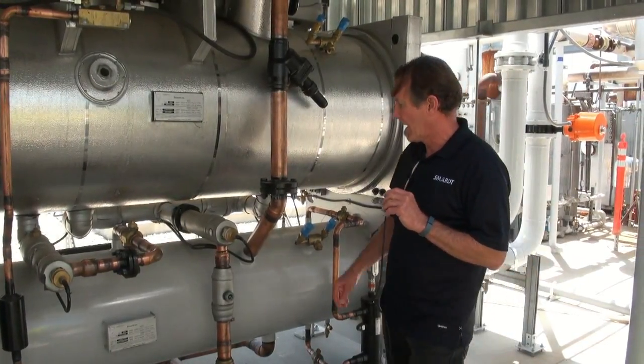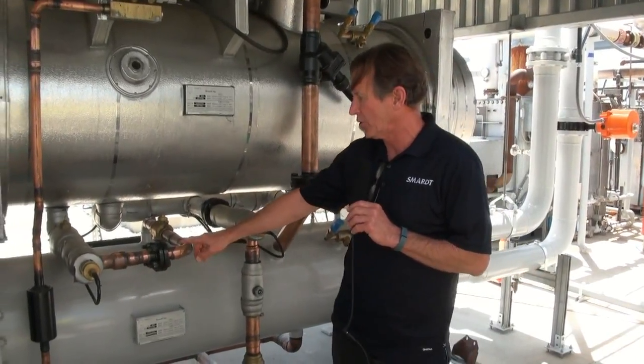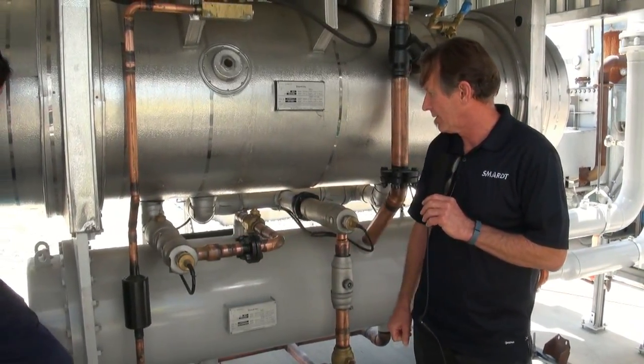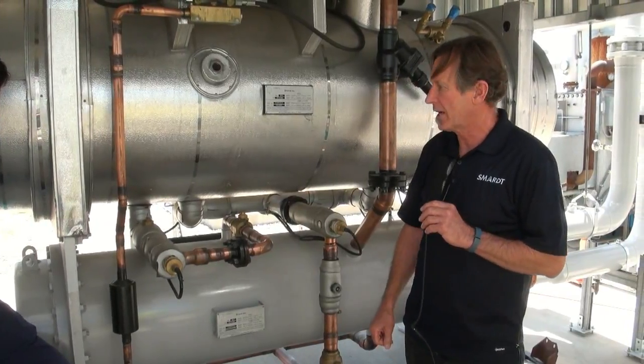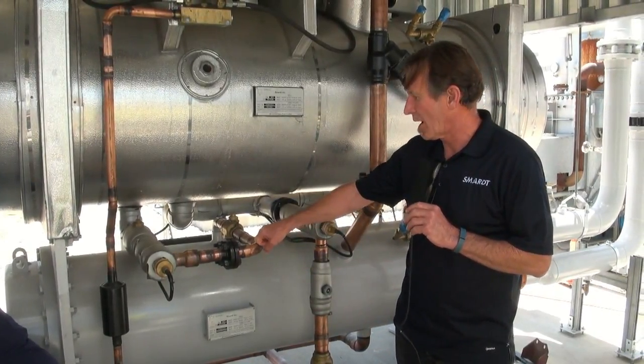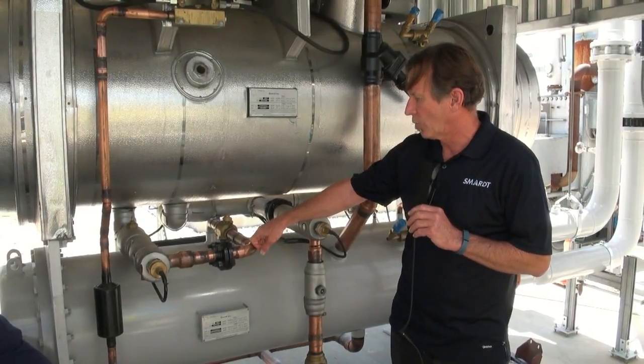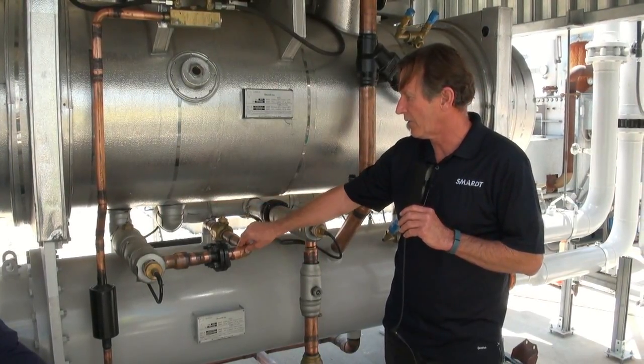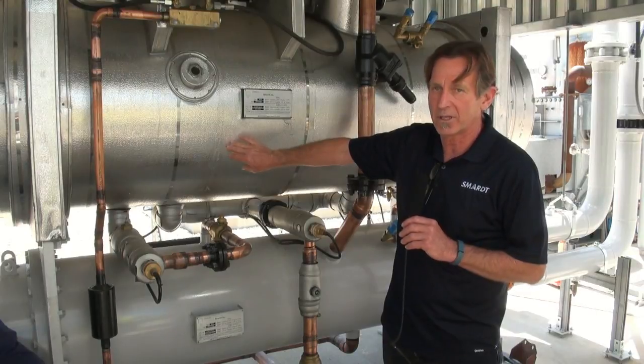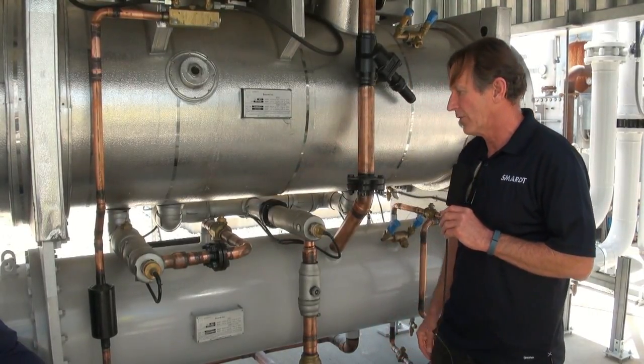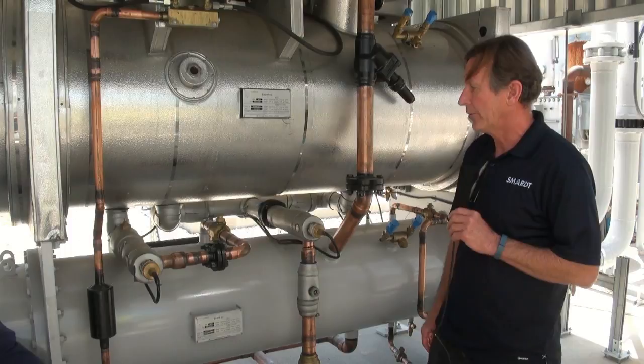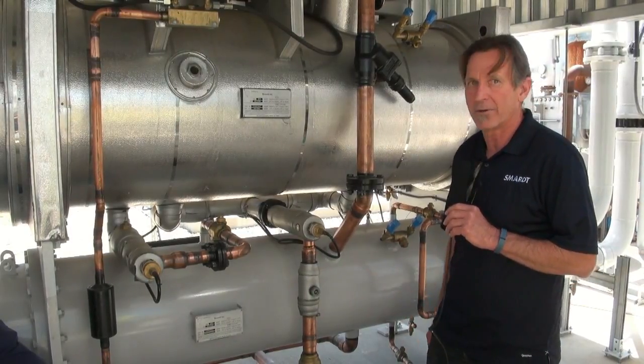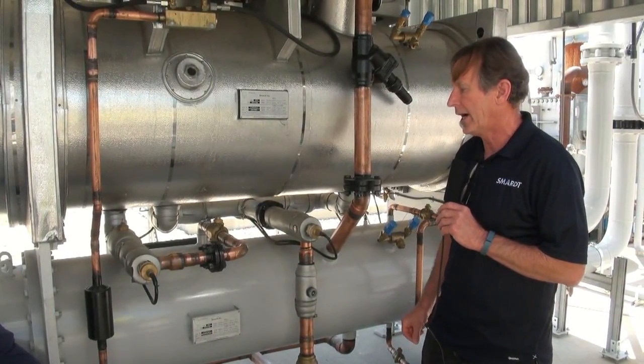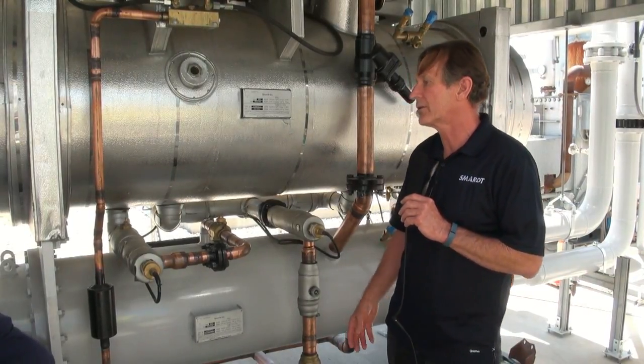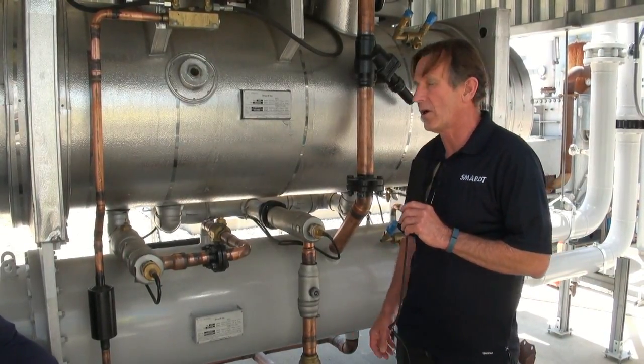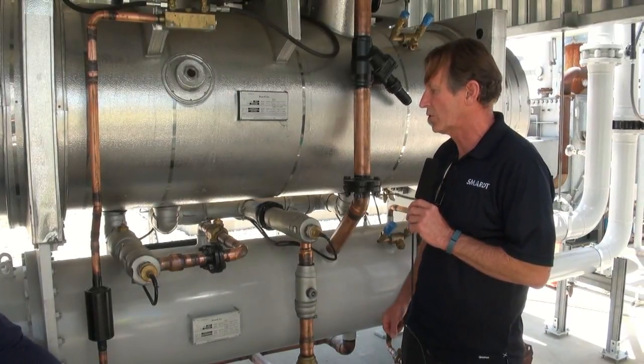We've got another expansion valve. It's the identical valve, but it's in use here as a hot gas valve. So we're just a bypass valve. We're taking high pressure gas off the top of the condenser, and when needed, the hot gas valve will open and put a false load on the evaporator. So there's a low load situation. We'll put that into effect to keep the chiller online if need be. Of course, if it can only do so much, it may cycle off the machine if the temperature gets too low, it'll cycle off.